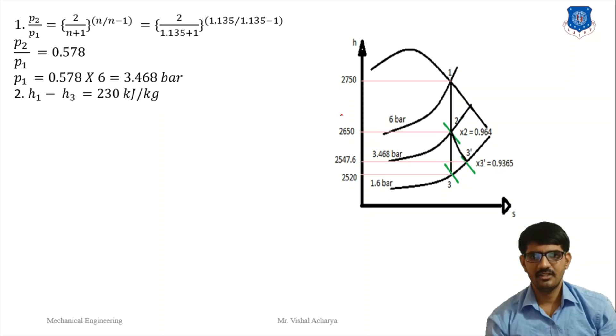The loss is 12% of the isentropic enthalpy drop, so the actual drop is 0.88 times 230, which is 202.4 kilojoule per kg. So we get the H3 dash value as 2547.6. H1 minus H2 is 2750 minus 2650, which is 100 kilojoule per kg. From the steam table, we find the specific volume Vg2 is 0.5321 and the specific volume Vg3 at the exit pressure is 1.0911 meter cube per kg. We multiply the dryness fraction by the specific volume. The volume at point 2 is 0.964 multiplied by 0.5321, equal to 0.513 meter cube per kg. Similarly, V3 dash is X3 dash times Vg3, which is 0.9365 multiplied by 1.0911, equal to 1.022 meter cube per kg.